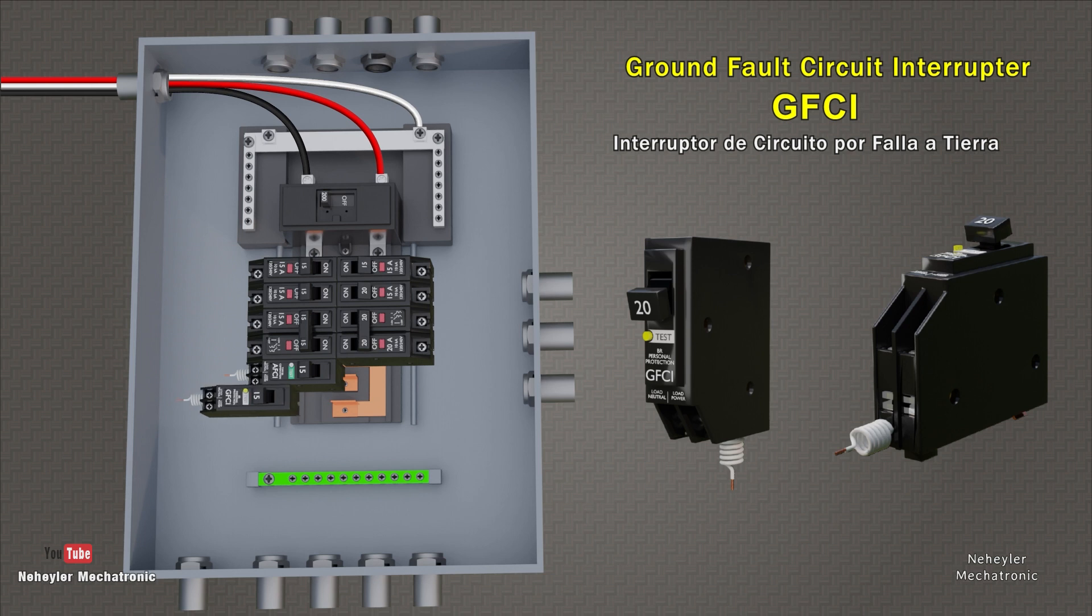Another important element is also the ground fault circuit interrupter. This device is designed to keep people safe from deadly electrical shock. When an electrical current diverted to ground exceeds a certain value, the GFCI switch interrupts the electricity immediately. These elements can be 15, 20 or more amperes in nominal current, and a sensitivity of 10 milliamps or less.